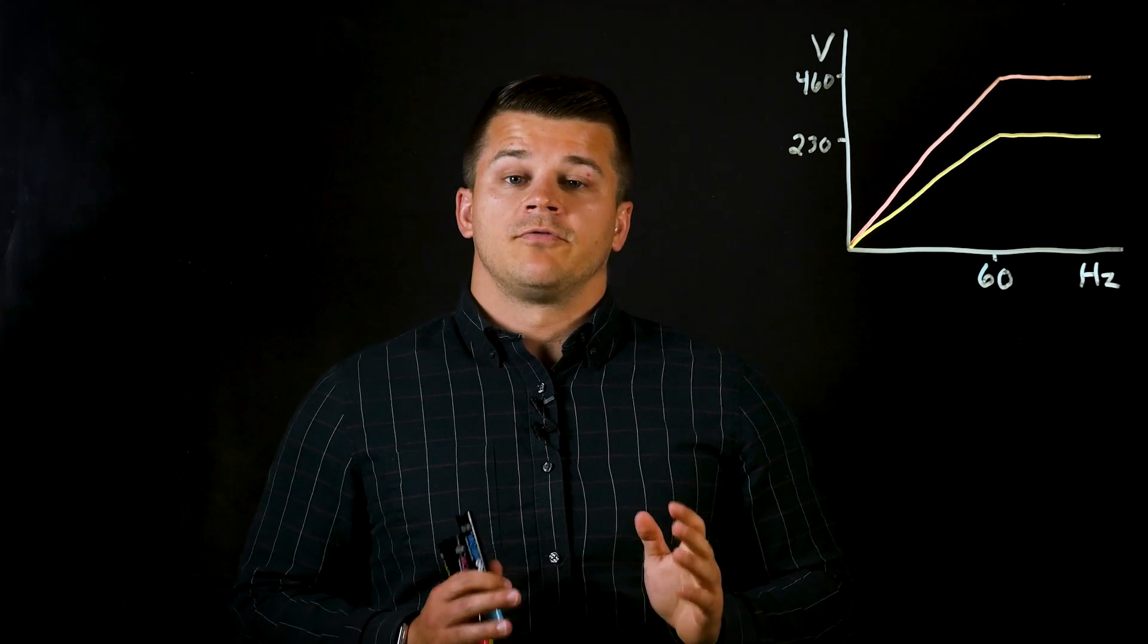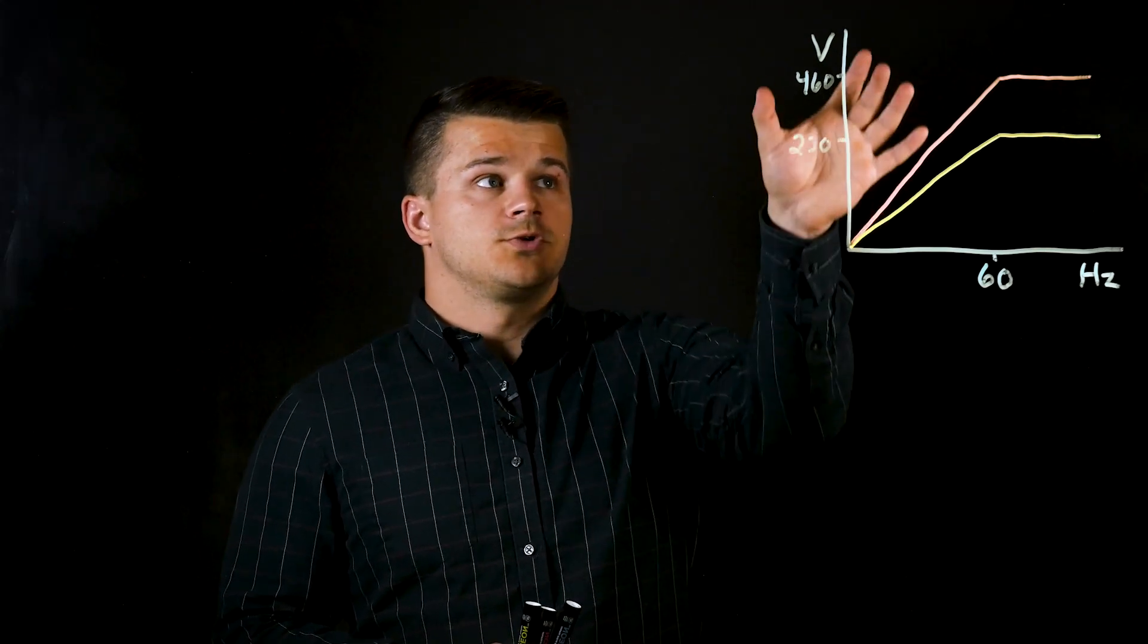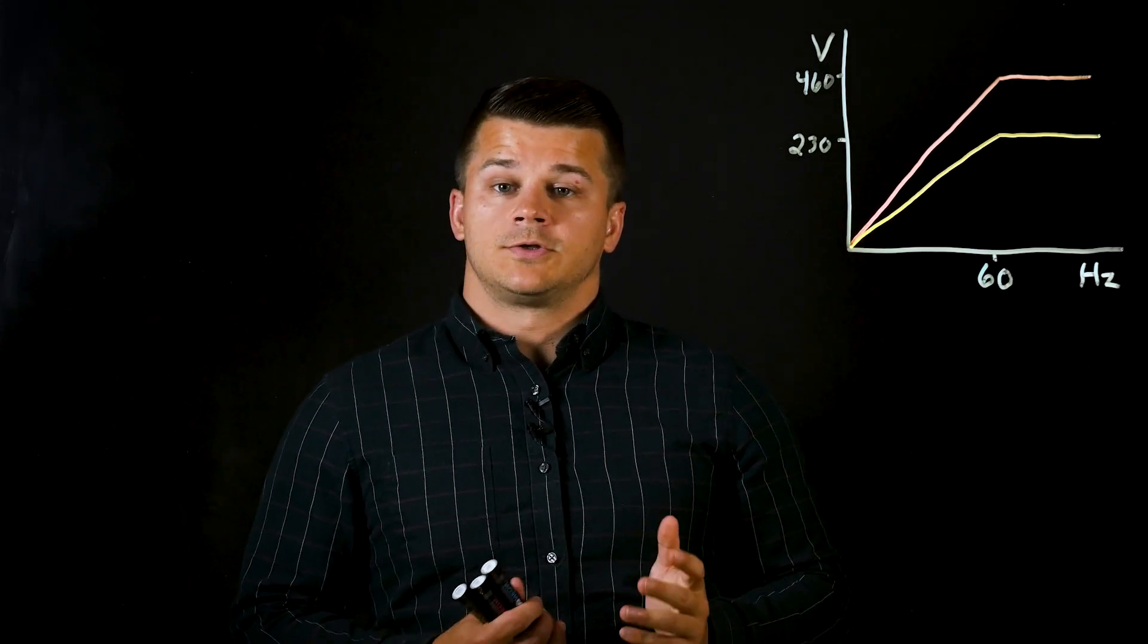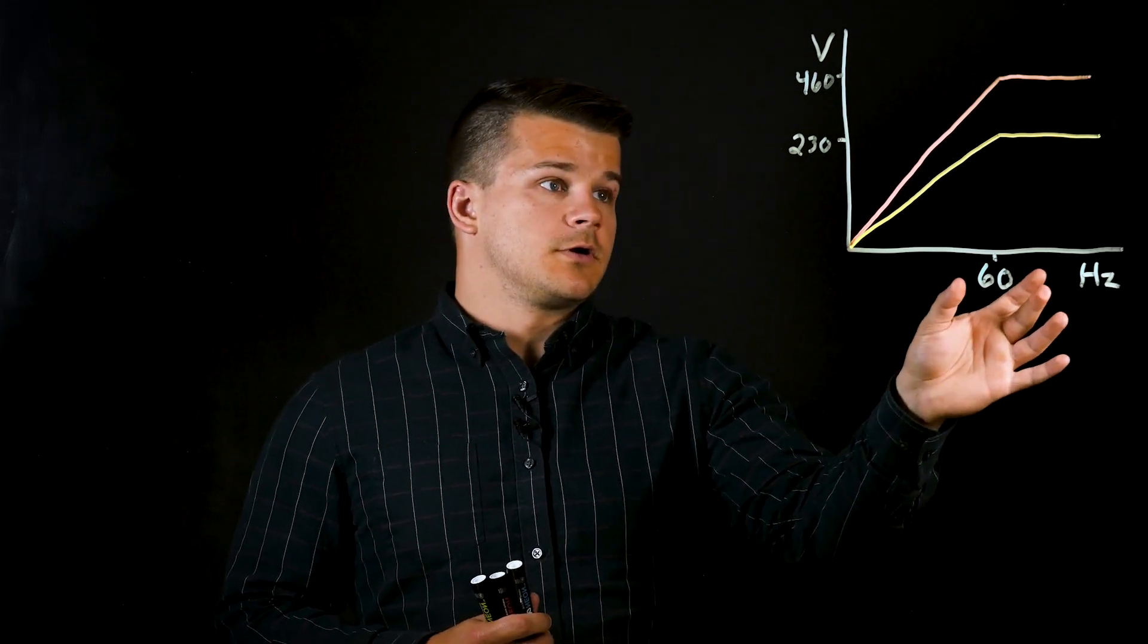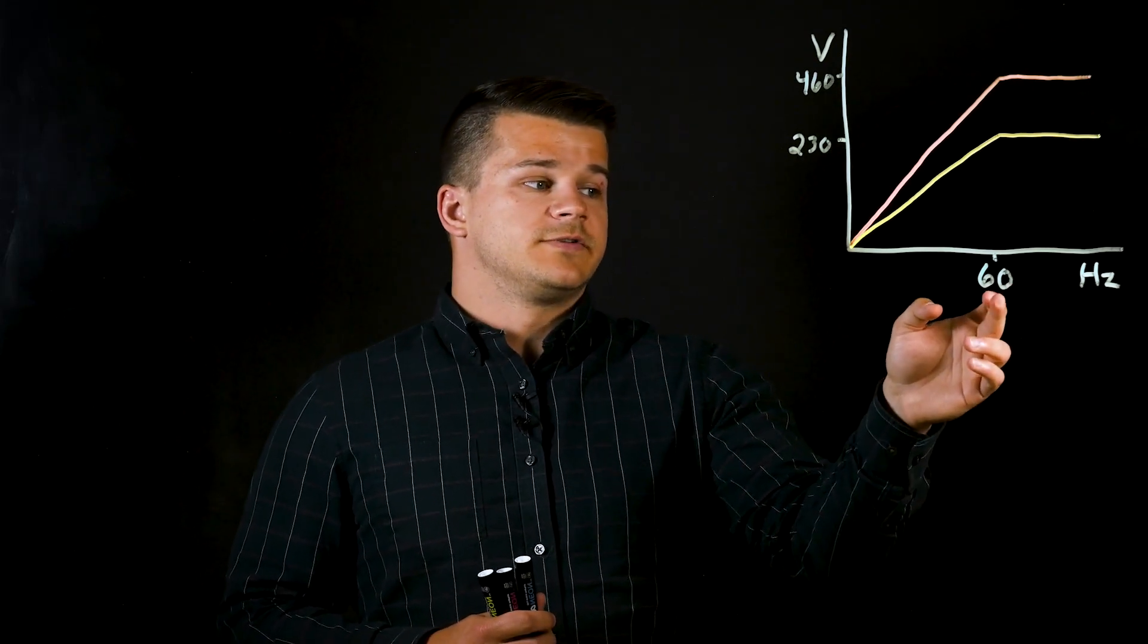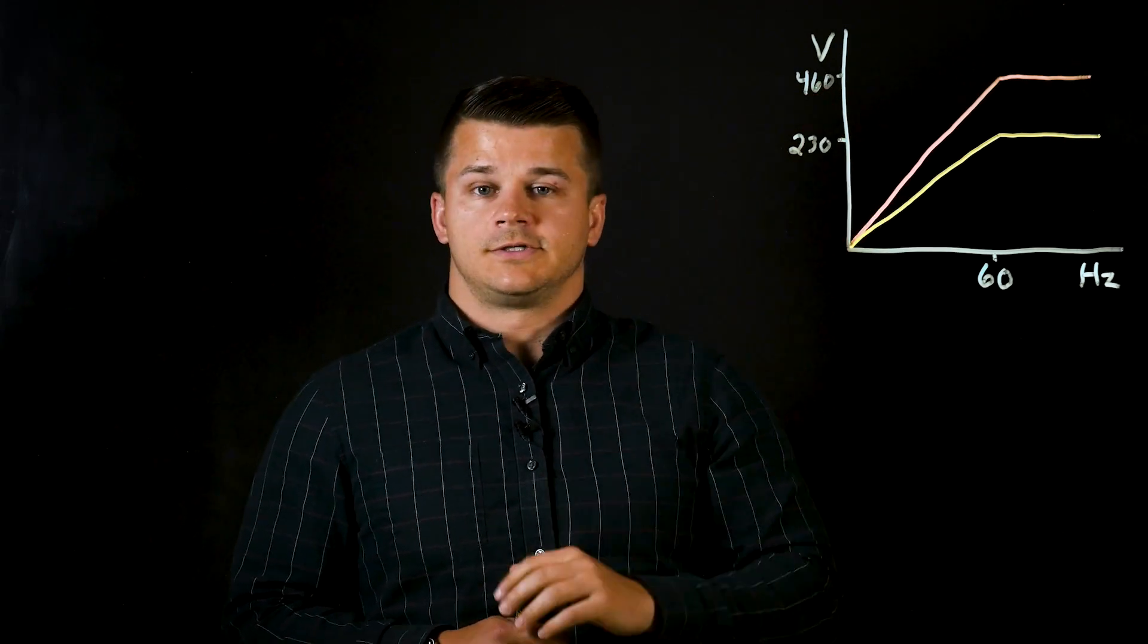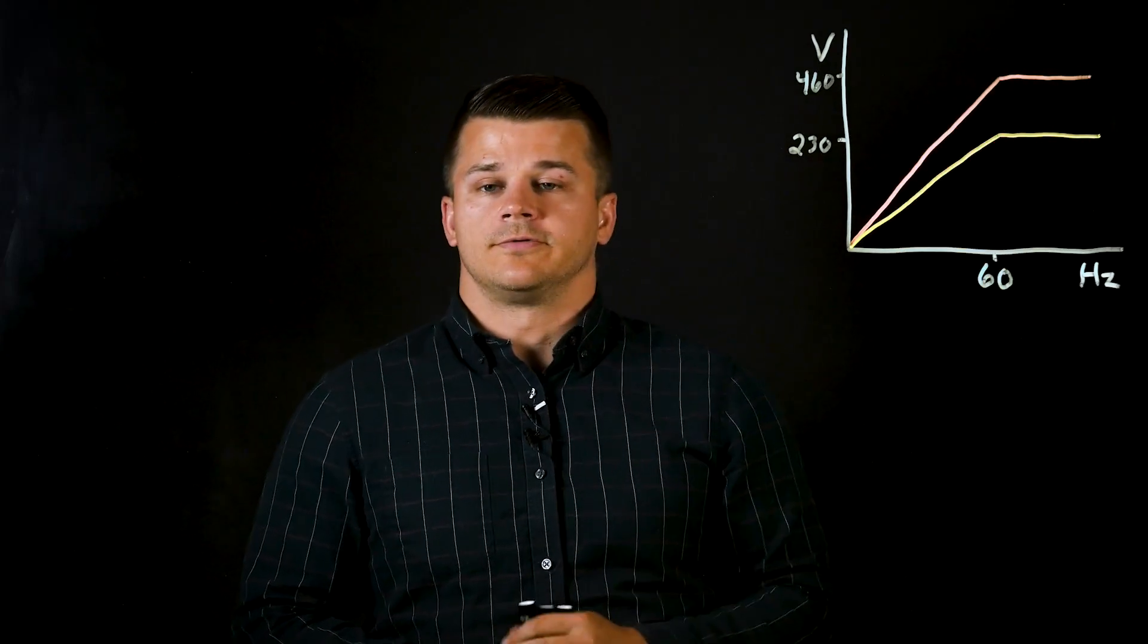So in a past video we talked about the volts per Hertz curve. The theory behind this is that by keeping the ratio between voltage and frequency constant, the motor will develop its rated torque until it reaches the rated point in the US, 60 Hertz. So in this case we have 60 over 230 volts or 60 over 460 volts. And we just need to keep this line straight until it reaches the rated frequency.